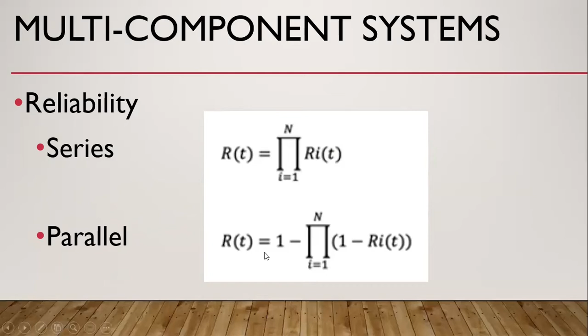This is the first example which I have taken. For a hematology analyzer with a mean time between failure of 180 days and an operating time of interest of 60 days, what is the reliability that the equipment will be functioning at 60 days? So the answer is that there is a 71.7% probability that the hematology analyzer will operate for the 60 days without failure. This is the utilization of this equation of reliability. This is the exponential model.